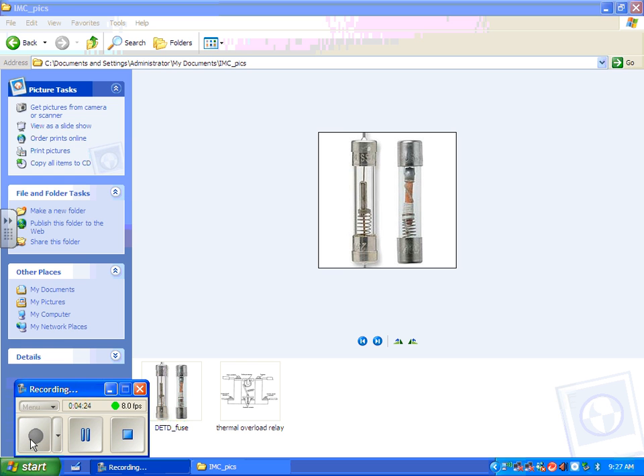Okay, let's talk about motor overloads. Motor overloads are what protect the motor from continuous excessive current, from drawing too much current. We've talked about, or maybe we haven't, that some motors cannot take any overload. Yeah, we have. We talked about motors having a rating. Anybody remember what that is? If the rating is 1.0, you can't overload the motor at all. If it's 1.15, it's called service factor. It's on the nameplate. We talked last week about the nameplate, remember? We talked about having a service factor.